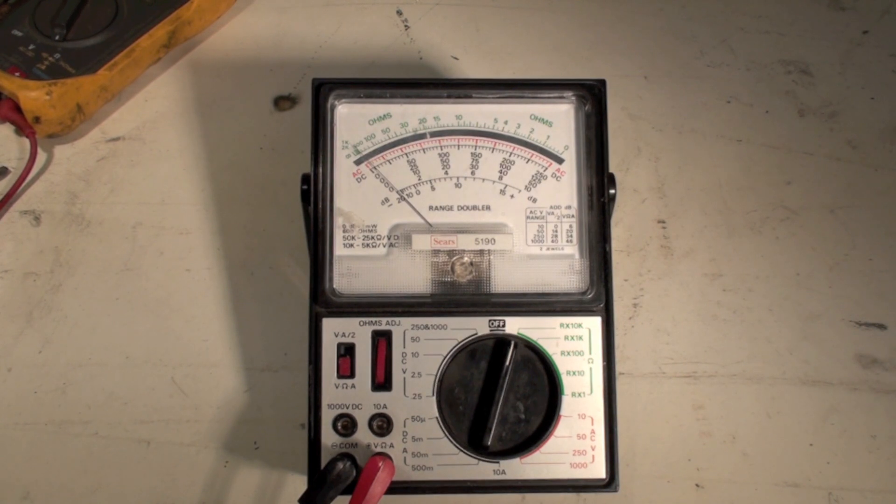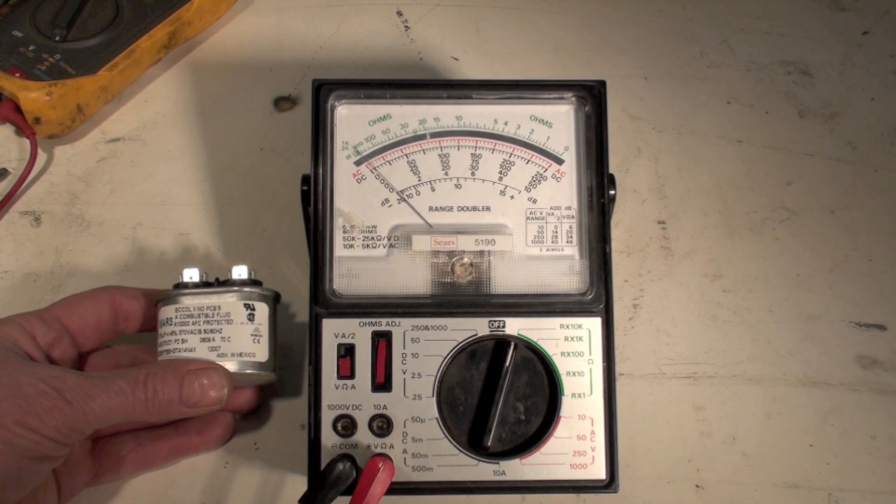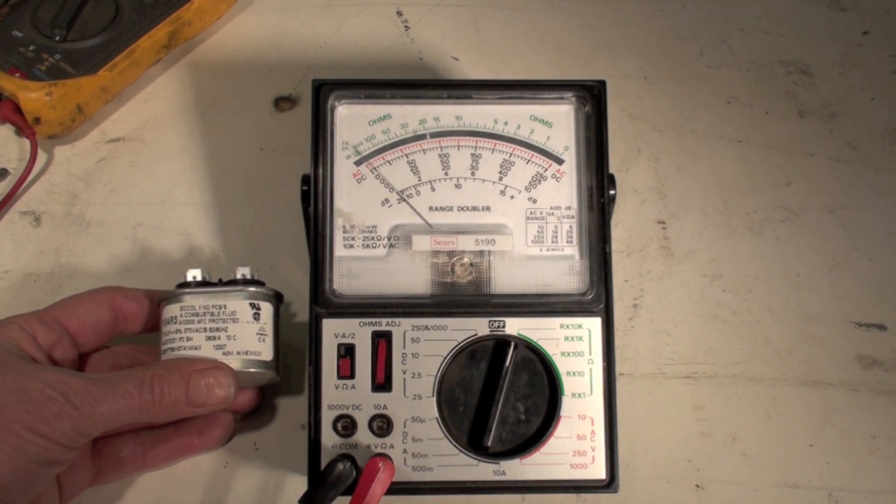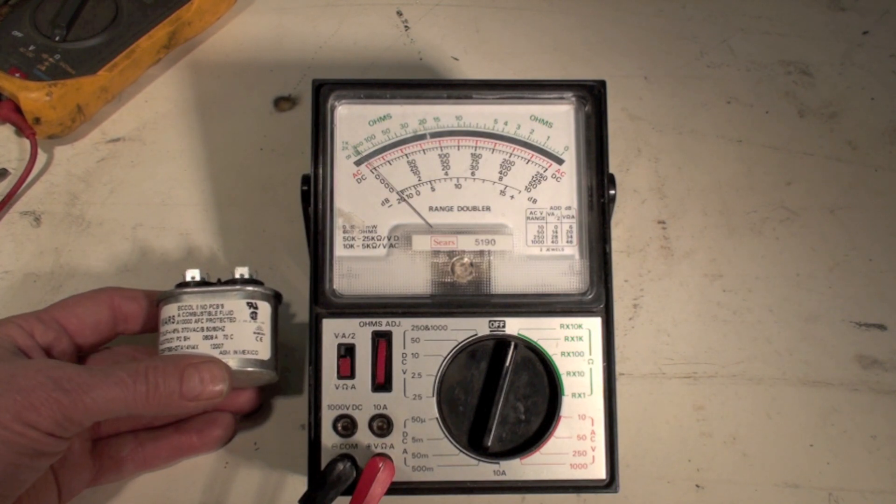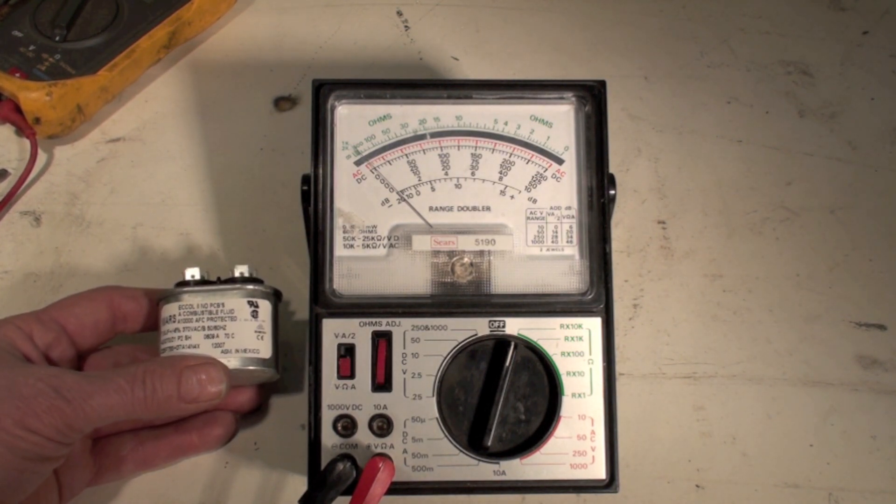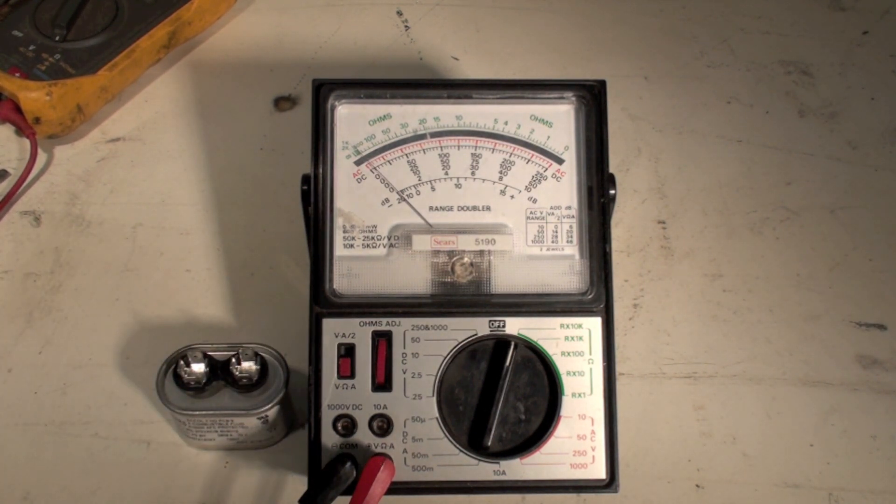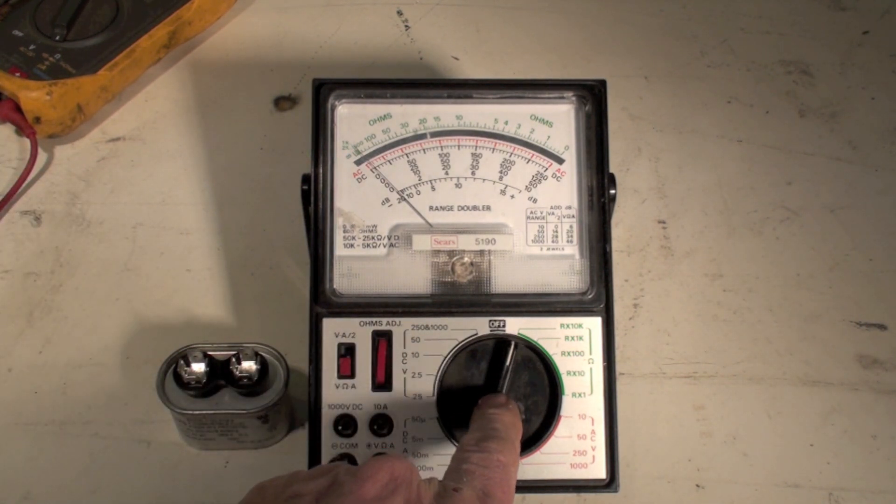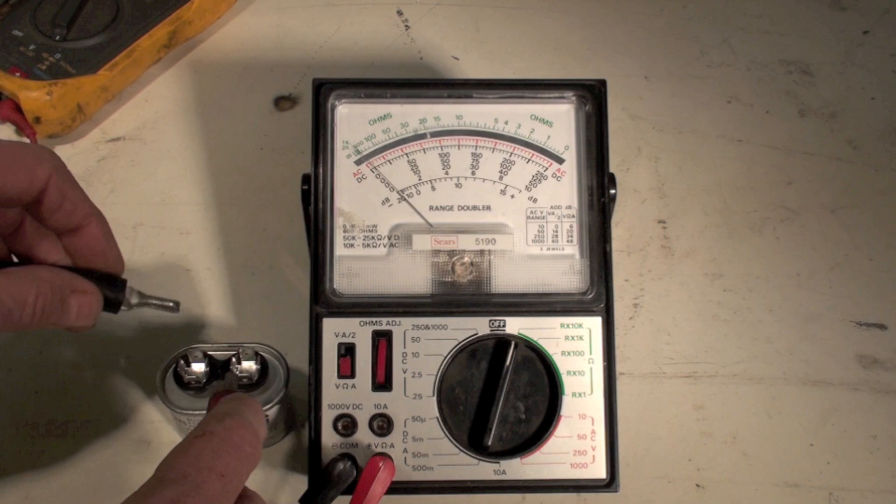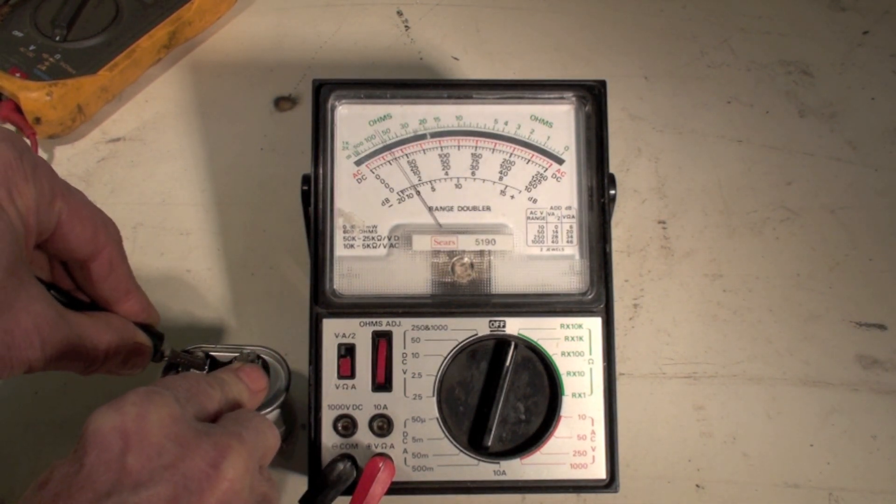This meter had one little thing that I used to use it for. Not particularly this one, it was a different one. But this is a capacitor, it's a run capacitor off a motor. And we did not have capacitor testers, or at least they were not common back then. So we use this as kind of a makeshift capacitor tester. And if I put the range in R times 10k, and I put my leads across this, you see it goes up, and then comes back down.